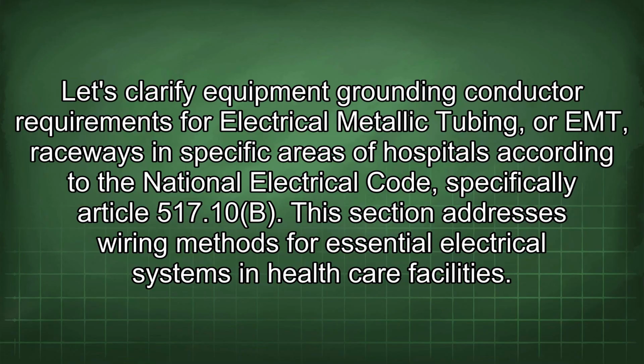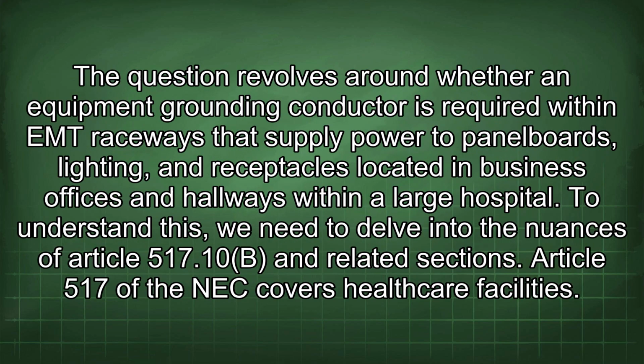Let's clarify equipment grounding conductor requirements for electrical metallic tubing, or EMT, raceways in specific areas of hospitals according to the National Electrical Code, specifically Article 517.10(B). This section addresses wiring methods for essential electrical systems in healthcare facilities. The question revolves around whether an equipment grounding conductor is required within EMT raceways that supply power to panel boards, lighting, and receptacles located in business offices and hallways within a large hospital.